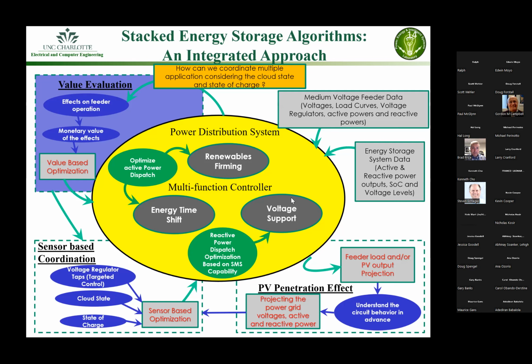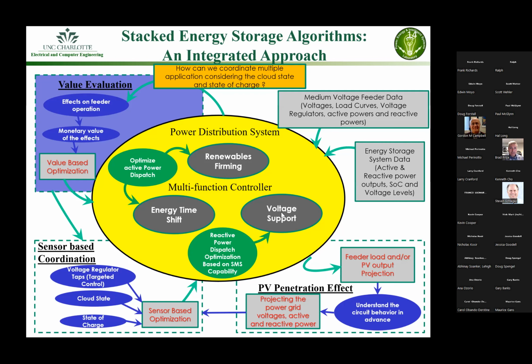The last one is voltage support, which has two different types. One is making sure voltage at specific points in the utility or distribution system is maintained, keeping the voltage profile quality good at that point. The second is the entire voltage profile throughout the feeder, coordinating with multiple legacy controllers such as voltage regulators, making sure they're maintained and controlled properly.